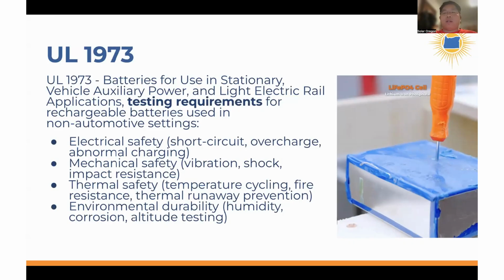Are there circuitries and battery management systems to prevent overcharging? And if that battery management system were to fail, will it cause a domino effect and lead the battery to explode? This is why I think most battery manufacturers have moved to lithium iron phosphate, and possibly in the future to sodium-ion battery chemistries, because these chemistries are much more inherently safe than NMC and lithium-ion chemistries of the past - those are quite dangerous if the safety circuitry doesn't work properly.